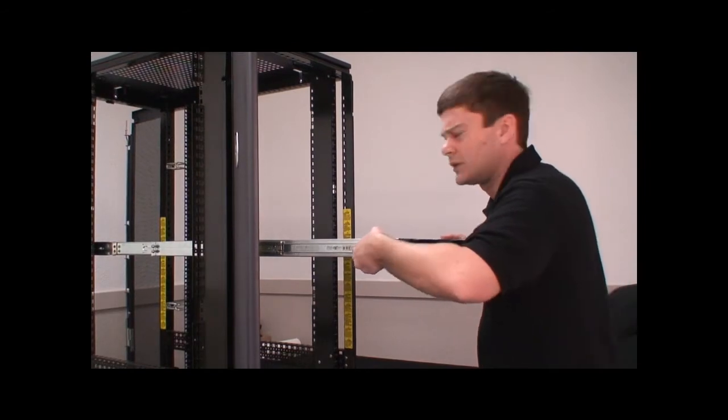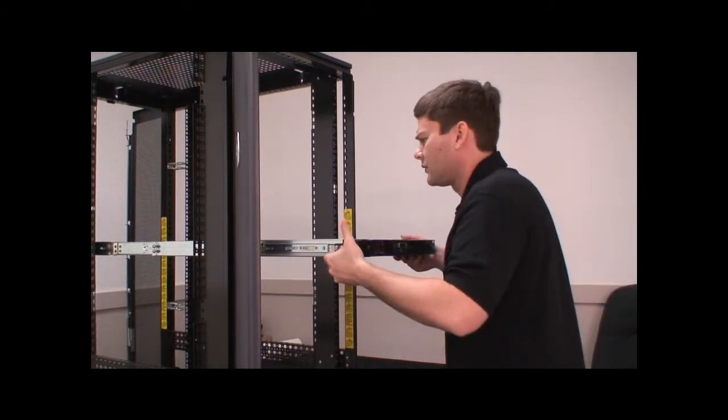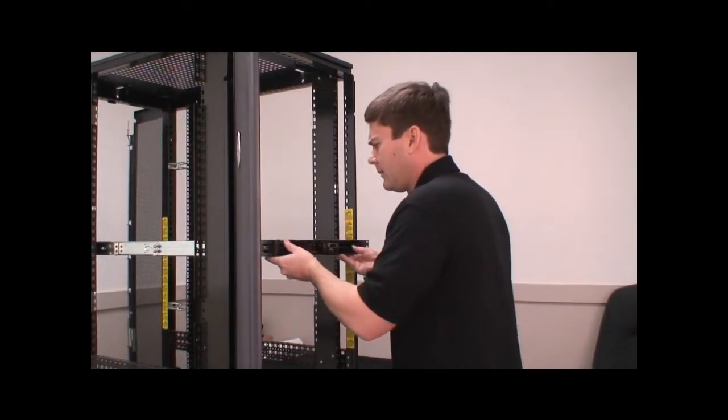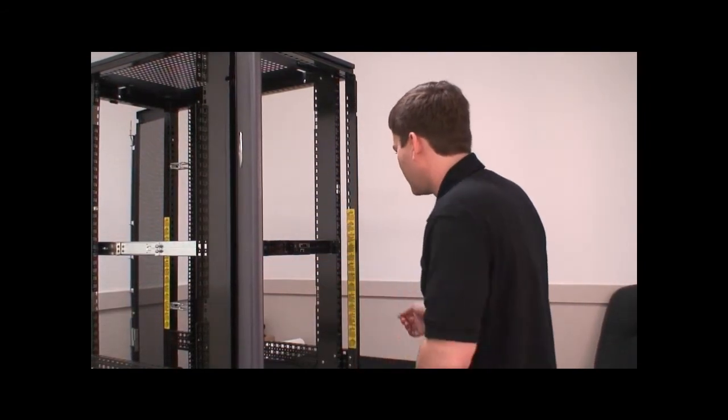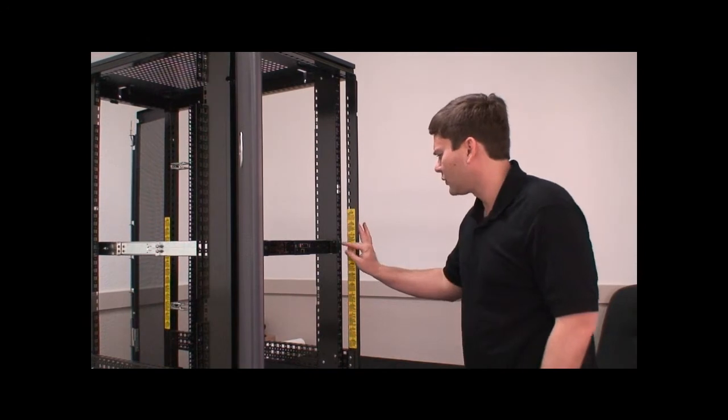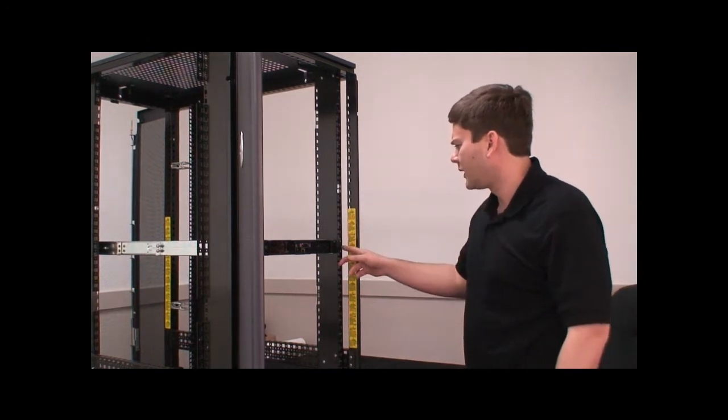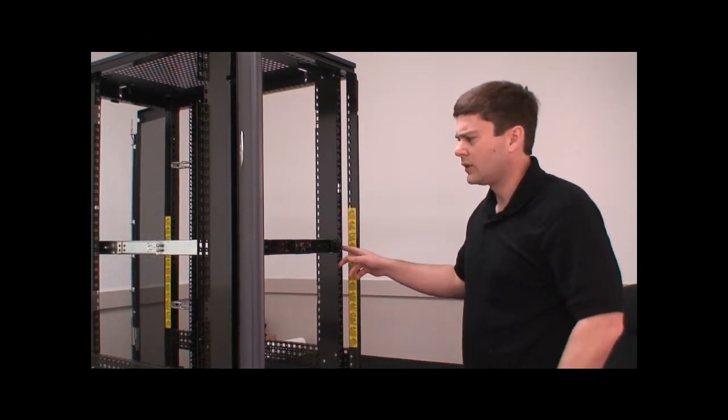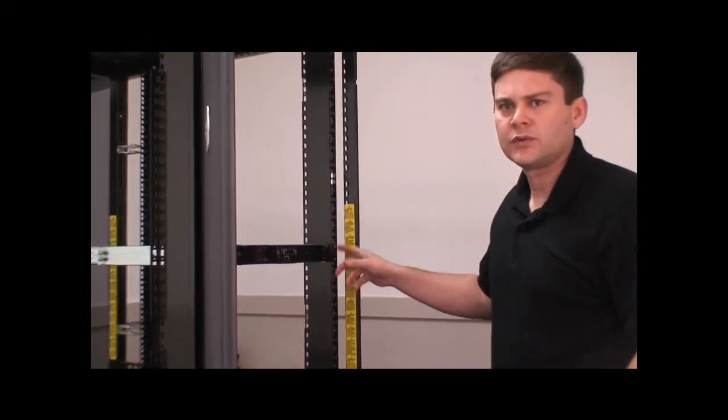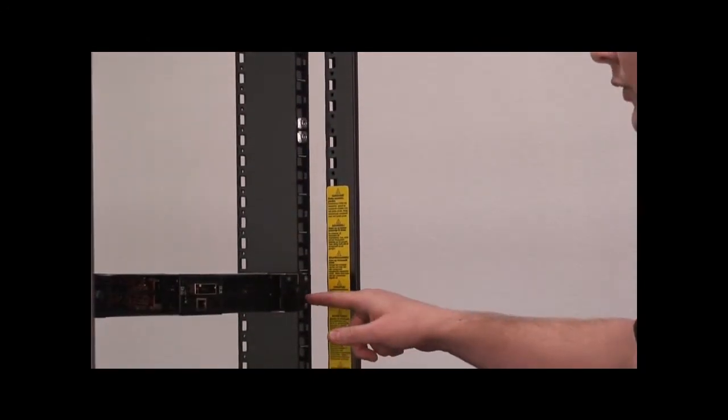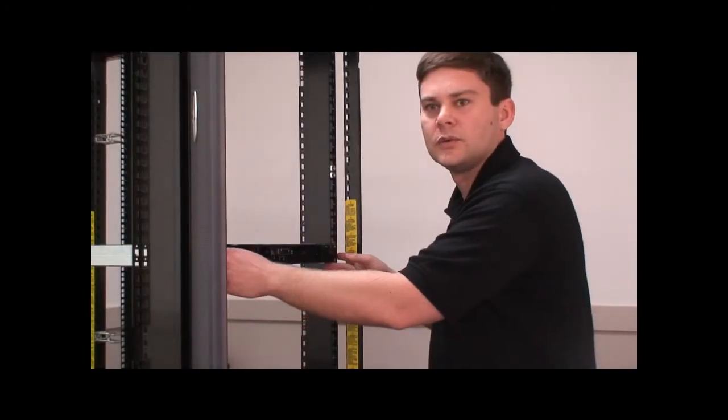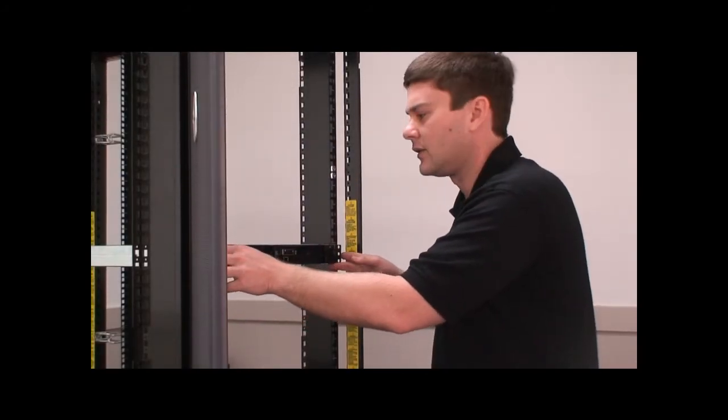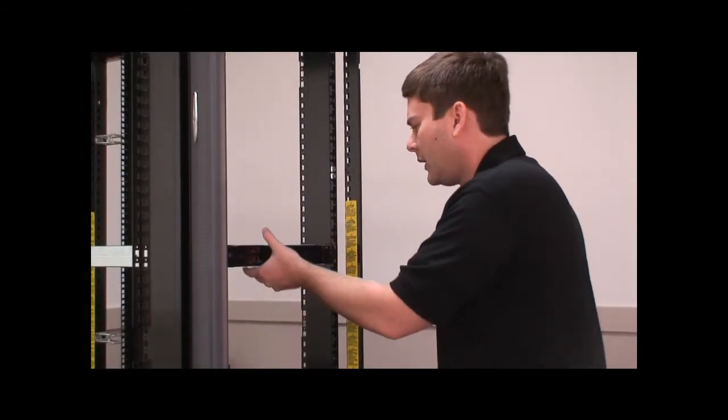We're pushing the chassis inside of the server cabinet now. Once you have it at this point, you would take thumb screws or any 10-32 screw. Some cabinets are 8-32. And use the center hole inside of the brackets to adhere the chassis to the cabinet.